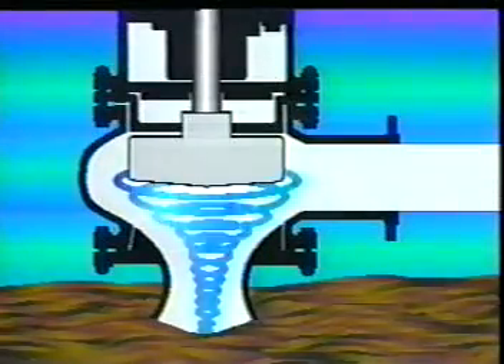A spiraling column of fluid of immense energy, passing down through the housing and through the hollow center of the intake. This rotor-induced, synchronized column of fluid agitates the material to be pumped — sand and gravel, silt, or sludge, for example. This powerful, swirling column of fluid creates a peripheral eddy effect, causing the agitated material to travel up along the sides of the intake chamber by reverse flow, up into the pump casing.